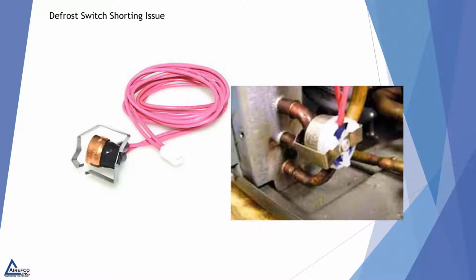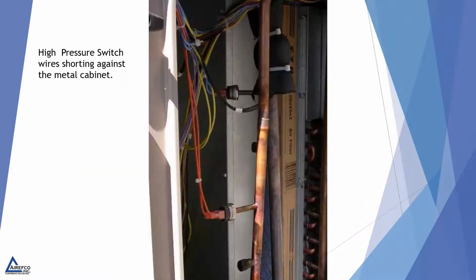That being said, there have been a couple of issues over the history of the product that cause shorts. One of those is the metal defrost switch found on many heat pumps to initiate defrost. This metal switch, when it fails internally and shorts to ground, grounds out to the copper tubing, causing the fuse on the control board to blow. By replacing the switch with a new one, you'll take care of your short issue.